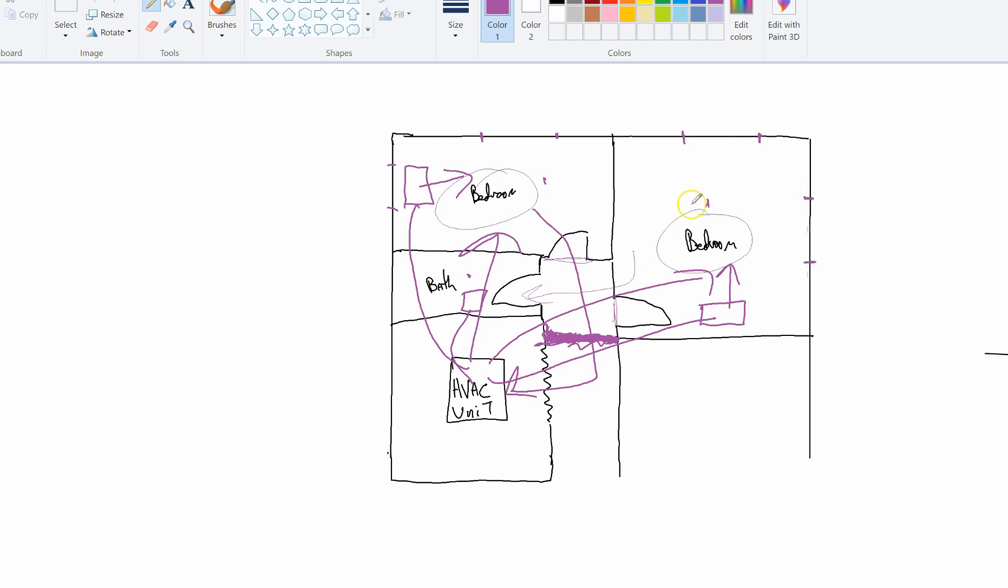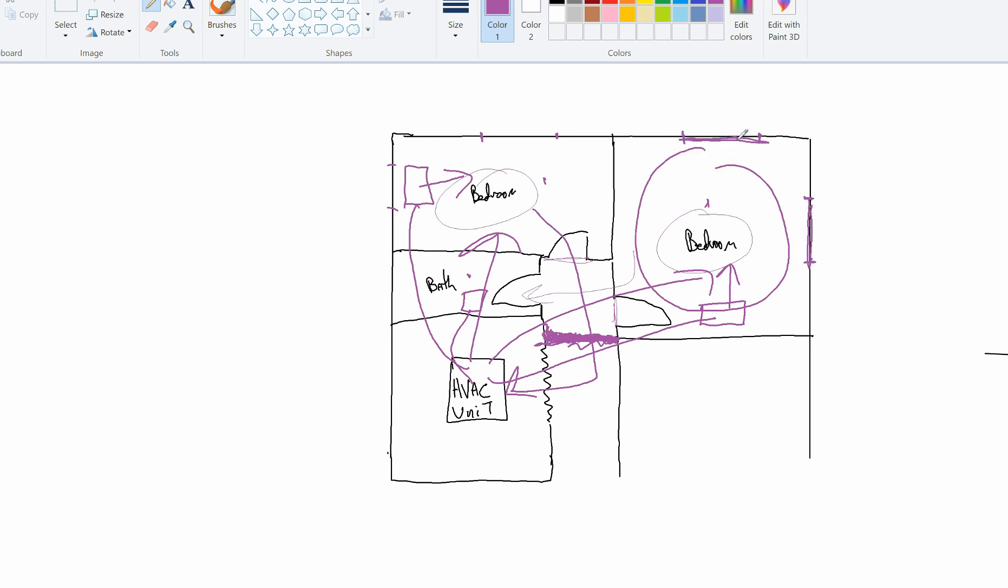which is going to create kind of like a balloon effect in these rooms because you're applying positive pressure into these rooms. You need to let that air out, so crack these windows about one-eighth of an inch to a quarter of an inch, and that's going to force the air that can't make it back to the unit because it's crashing into this wall, so to speak. You're going to make that air go out.